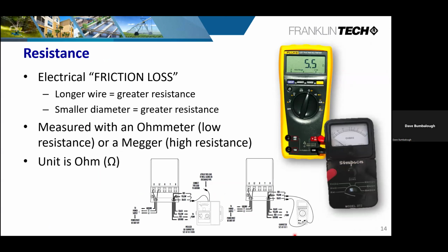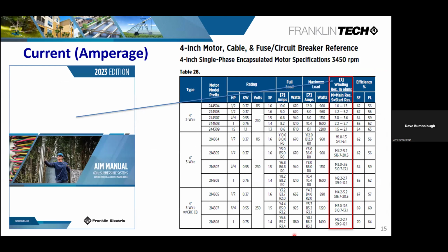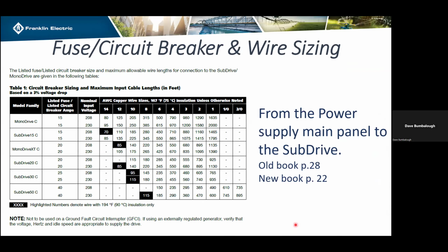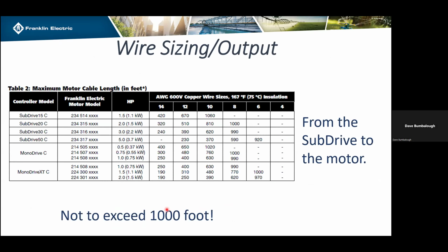The other meter that we're accustomed to using is our ohm meter, checking for resistance. We can also do this using the insulation tester, which is referred to as the Megger. When we're checking these, basically all we're looking for is to make sure that something hasn't happened to the windings or the wire itself. And again, you can always refer back to the manufacturer's manual and see what those values need to be as we're checking that circuit electrically. Wire sizing and breaker sizing, some manufacturers produce those, and you've got to pay very good attention to what they're suggesting there, because this is based off of National Electric Code values and tolerances. So always pay attention to the manufacturer's recommendations going forward. Going on, if we're looking at a drive, going from the drive to the motor, typically there are filters inside the drive, and we want to be very careful that we've not exceeded the threshold those filters are designed to work at, and that's typically around 1,000 foot.